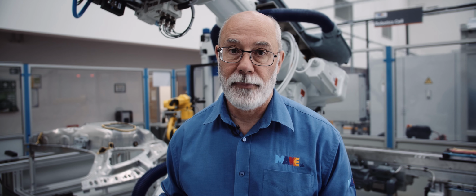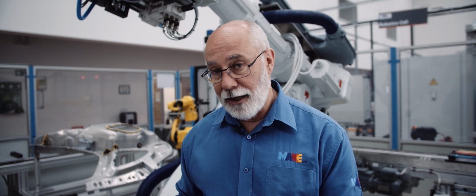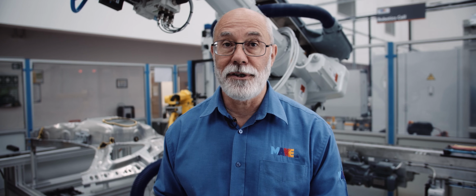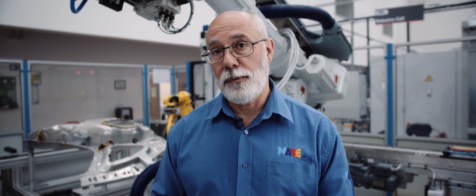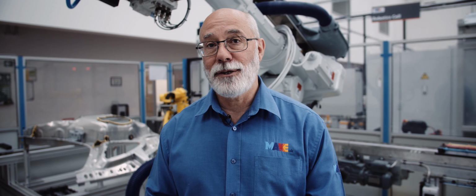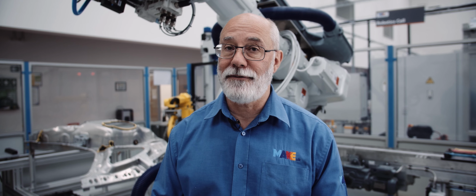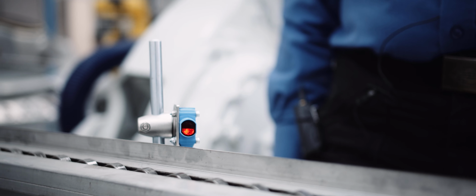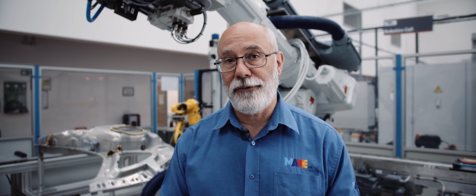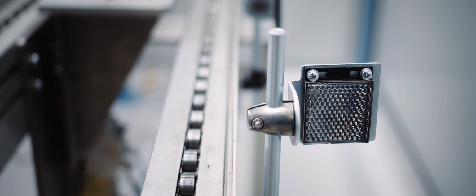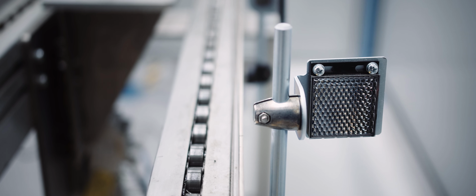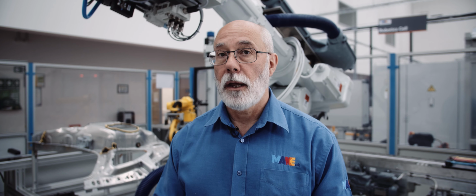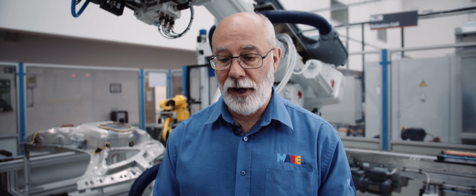Having looked at the cell, I can see that it's got a green power light on it, so I know the cell itself is receiving power. What should also be getting is an amber light next to it, which tells me it's getting a signal back from its reflective plate. When I look across at where the photoelectric cell is pointing, I can see that the reflective plate has moved. So, first question I'm going to ask is, why? Why am I not getting a signal? The plate's moved. Second why: why has the plate moved?